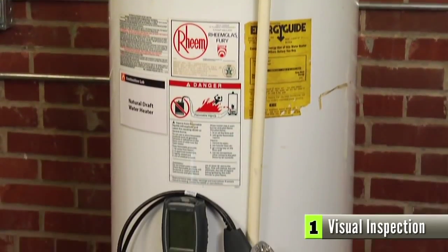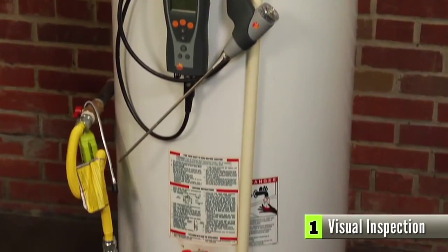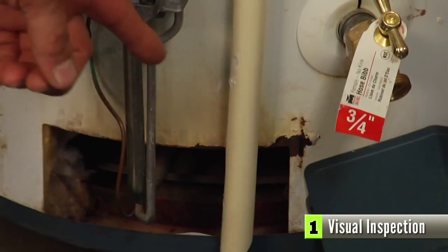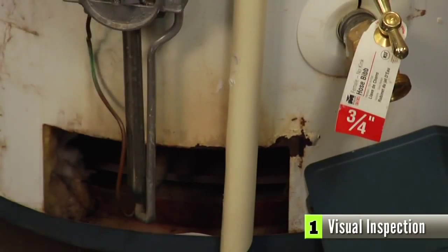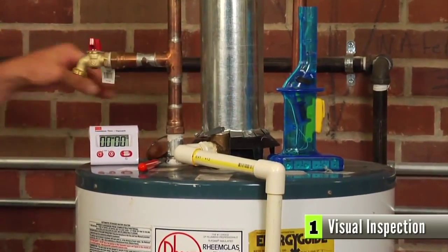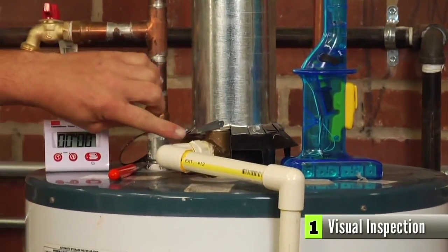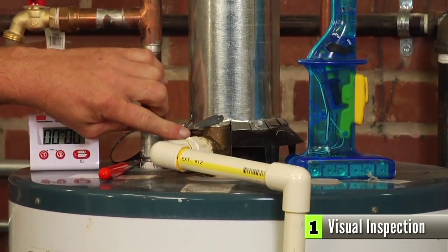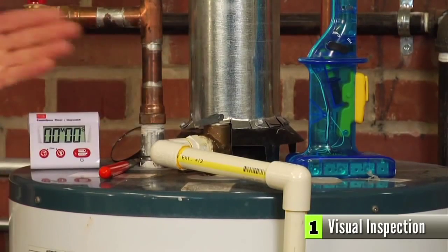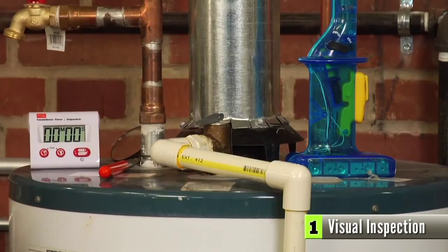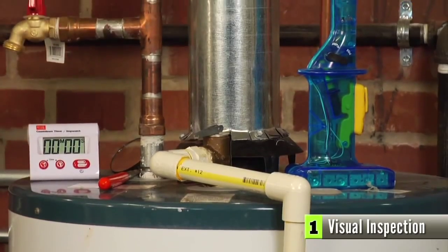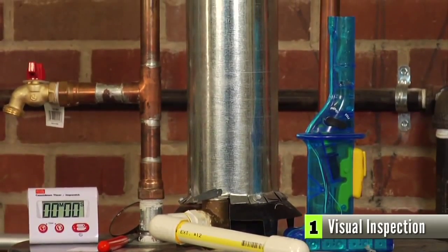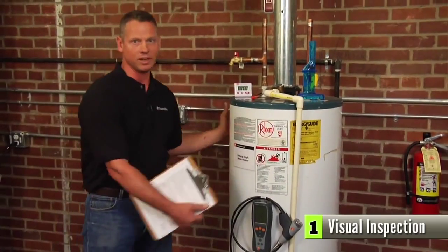Next, we'll inspect the condition of the appliance. This should include signs of rusting anywhere on the appliance, like here, and any condition of the draft diverter, this black ring. If this draft diverter is missing or smashed or rusty, then that could cause a problem that would allow the flue gas to escape past the flue up into the house. And check for any pre-existing insulation wrapped around the appliance.